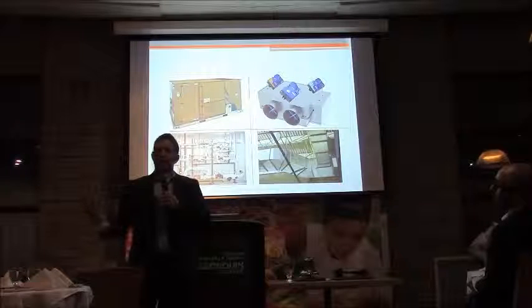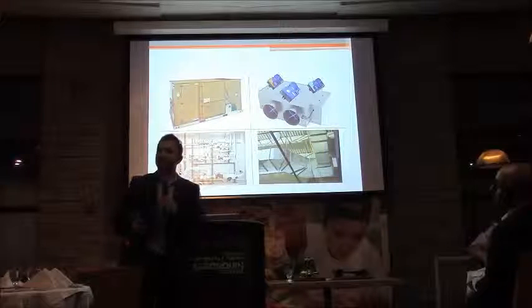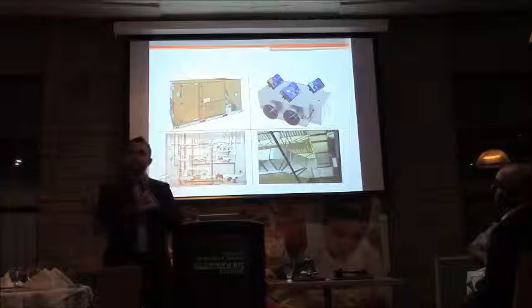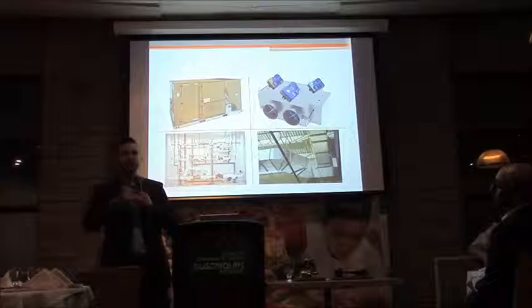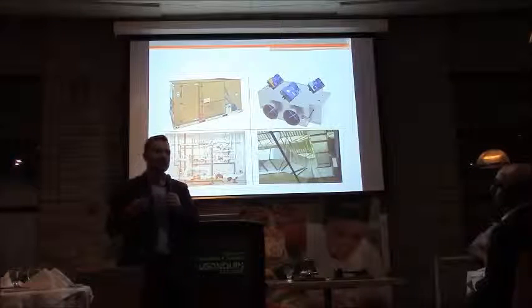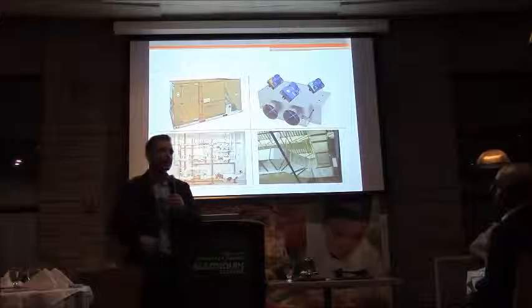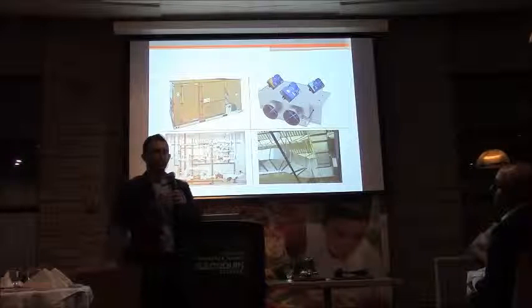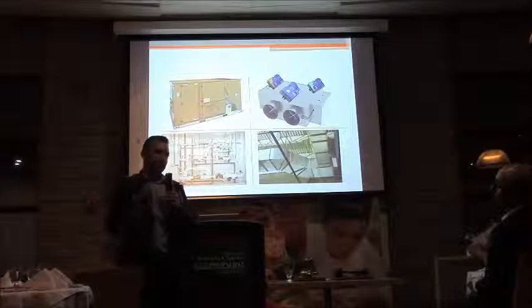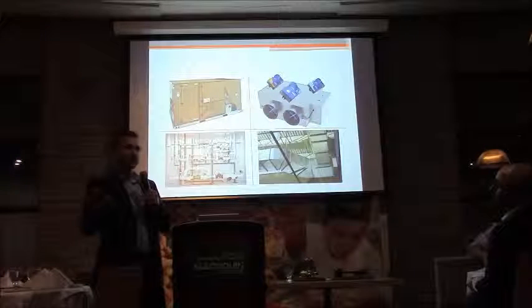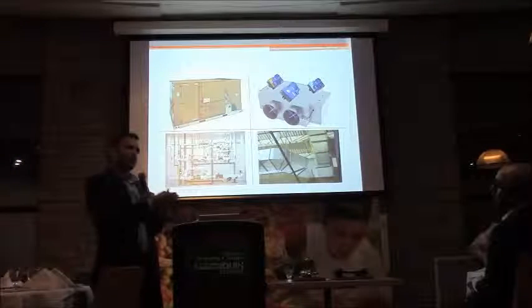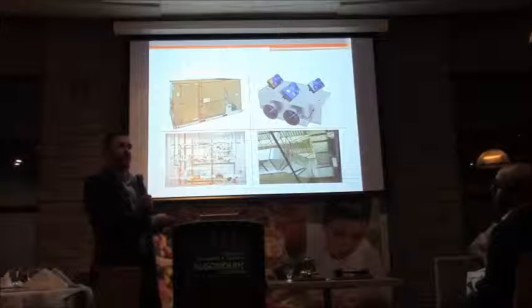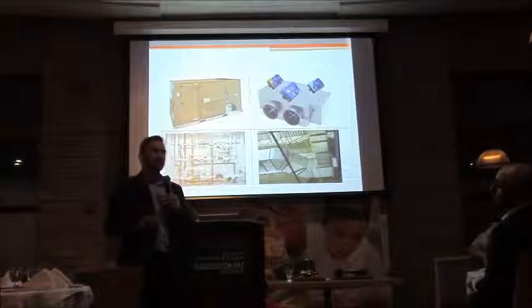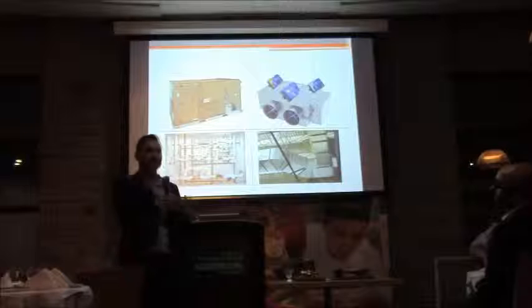Typically, we're going to select them for maximum airflow, because if you did it the other way around and selected at minimum, once you reach maximum, you're going to have a lot of noise issues, static pressure losses, too much throw. So we select for maximum airflow, and we kind of hope for the best once it reaches minimum airflow. But the real answer is you need to select a diffuser for maximum and minimum airflow.